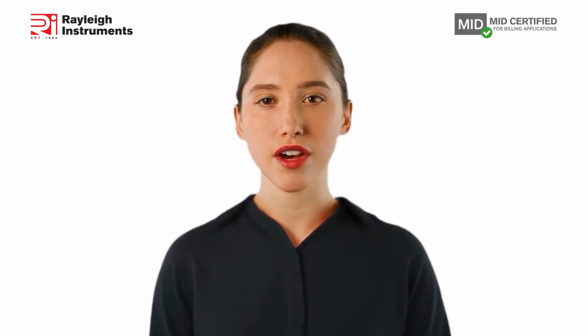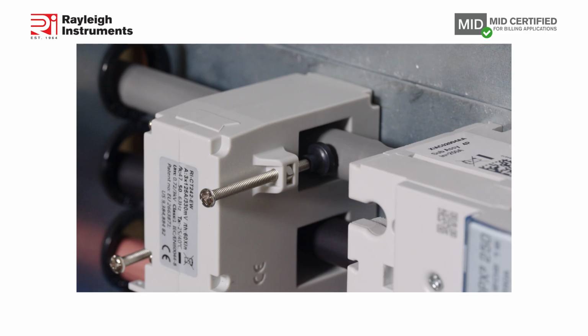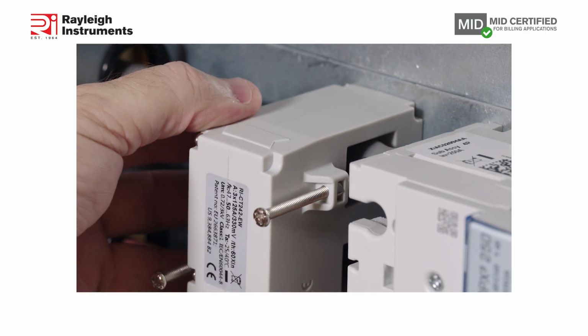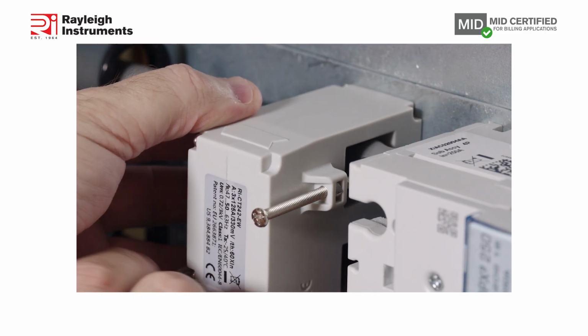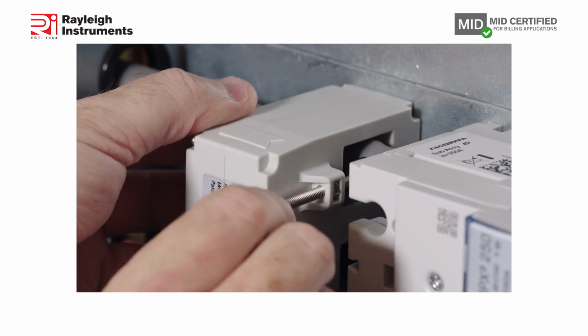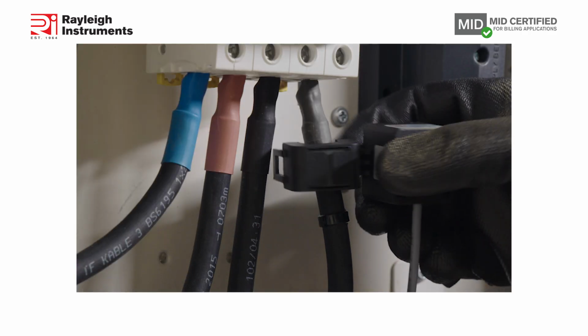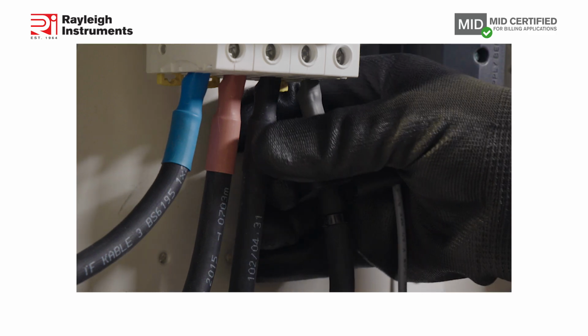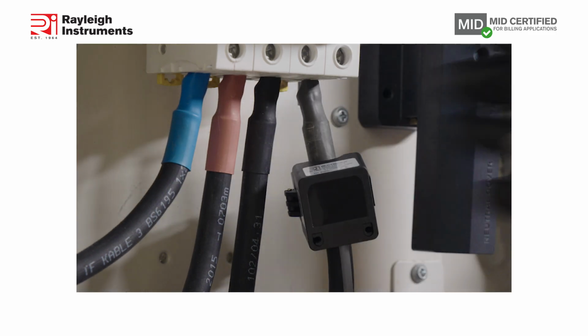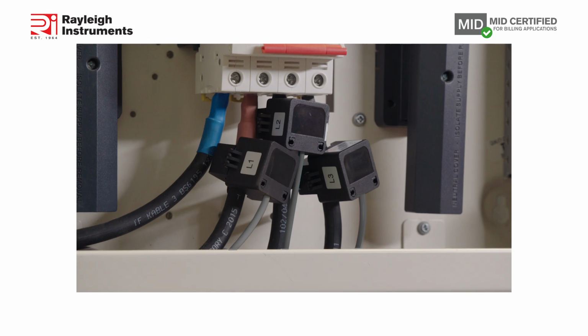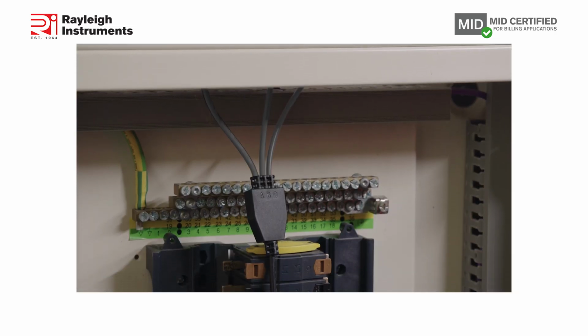All our 3-phase current transformers also come with bus bar fixing clamps and load direction arrows molded on the CT shoulder to aid with correct installation. For retrofitting applications, we also have a mini 3-phase split core solution, which also has integral overload protection and Easywire connectivity.